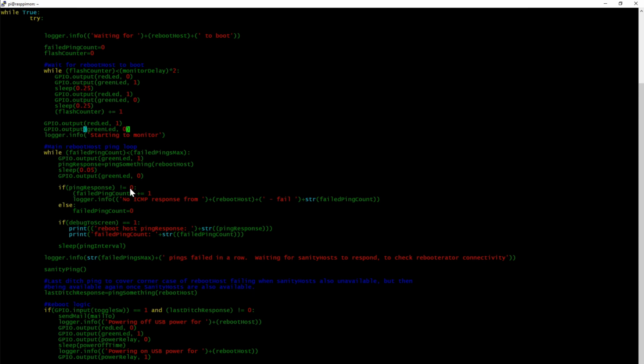So basically, if you don't get a 0, you add 1 to the failed ping count, and when the failed ping count gets to failed pings max, then we do the power cycle. But you only need to get 1 ping back to reset that count back to 0.